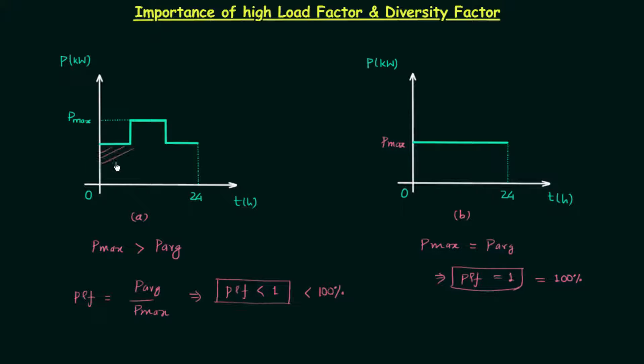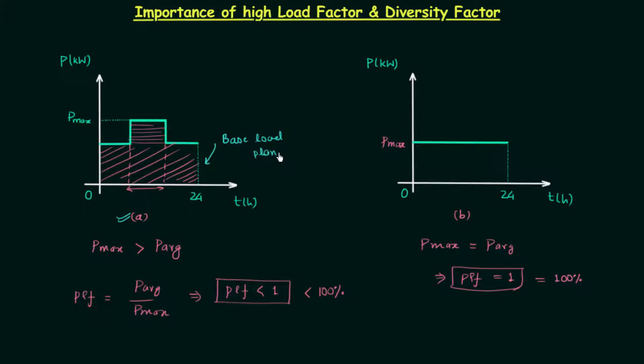In load curve A, there is a base load — a power demand that is always present — and also a peak load with a corresponding peak load duration. So load curve A has two types of loads: base load and peak load. Because of this, to satisfy load curve A we need two types of plants: base load plants, which are operational throughout 24 hours, and peak load plants, which operate only during the peak load period.